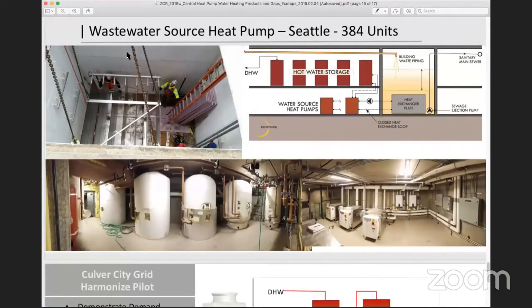Here's a unique one that we just wrapped up. It's a wastewater source heat pump. Right now the focus is all air source, but wastewater source is definitely something to keep in mind. We ran a simulation on this, and the COP came out to right around just under 4 seasonal. So there's potential - we haven't seen the results out of this yet, but this is the project, and we just wrapped up commissioning on it. It's pretty interesting, so we'll have some more to report on this next year.